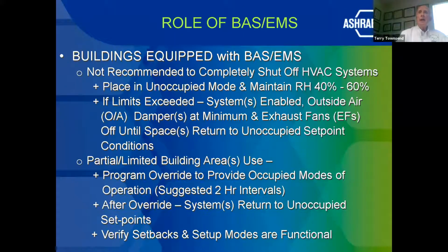Outside air dampers are off, and what you're doing is bringing just the space down into the 40 to 60% relative humidity range. If there are partial or limited use areas, have a program override, possibly as suggested at 2-hour minimum intervals. After the override, the system returns to unoccupied set points. And then what you need to be able to do is verify these setbacks and setup modes are functional. The systems that are enabled have outside air at a minimum, and exhaust fans are off until it returns to an unoccupied set point condition.